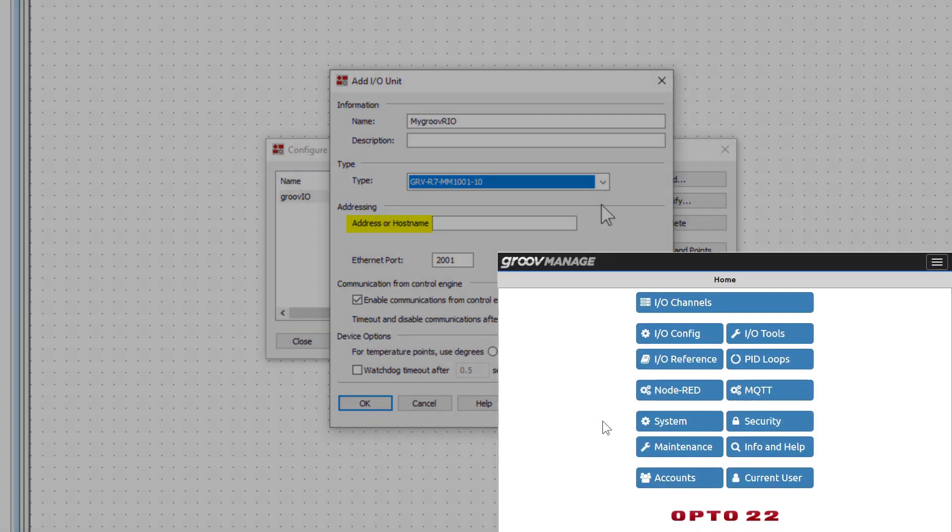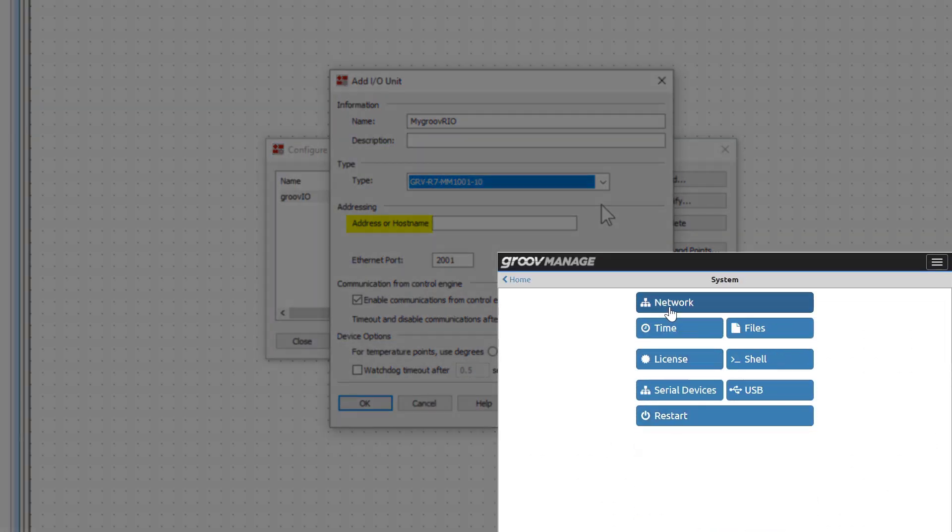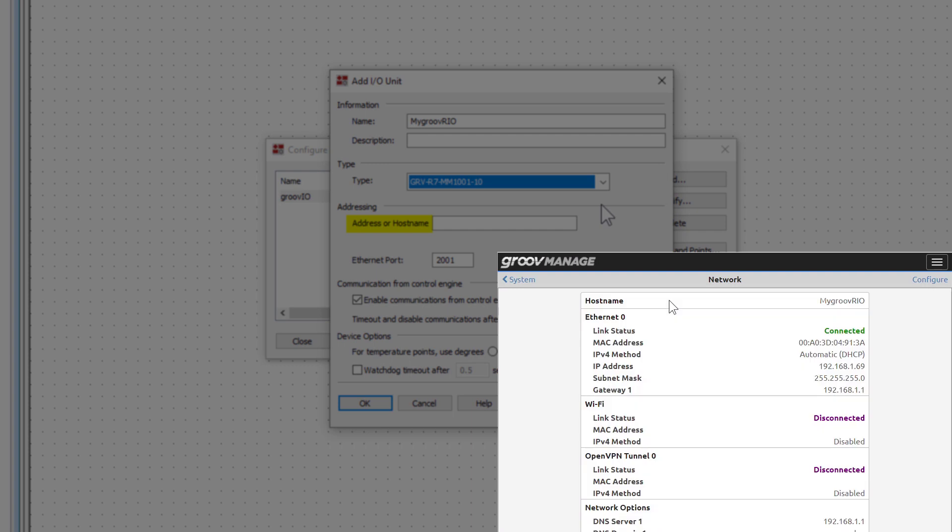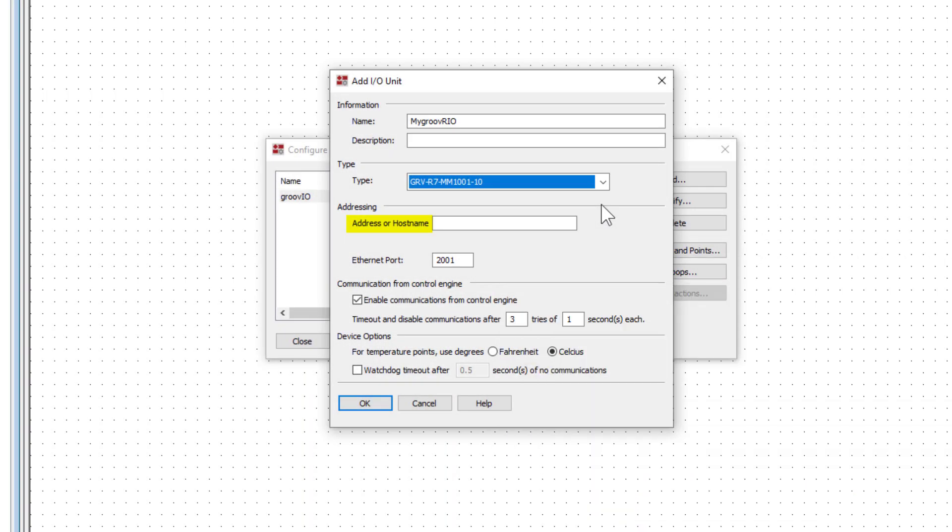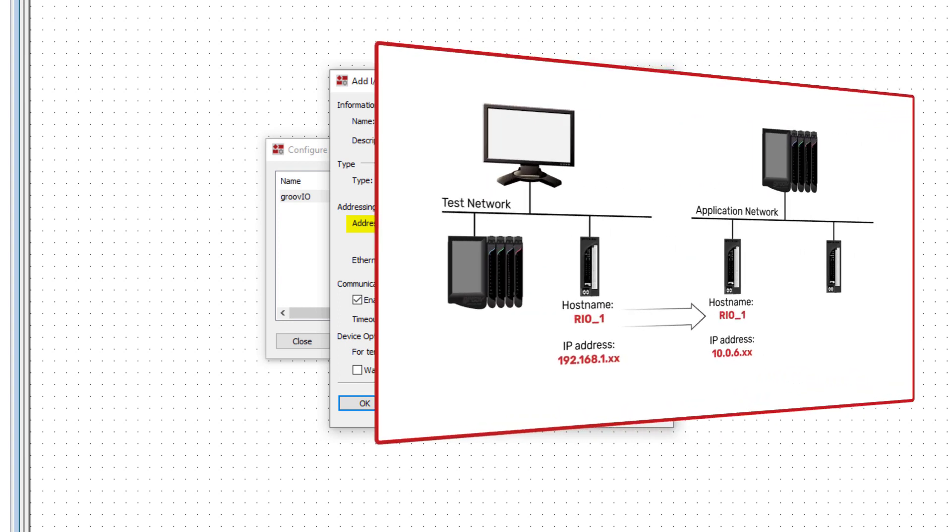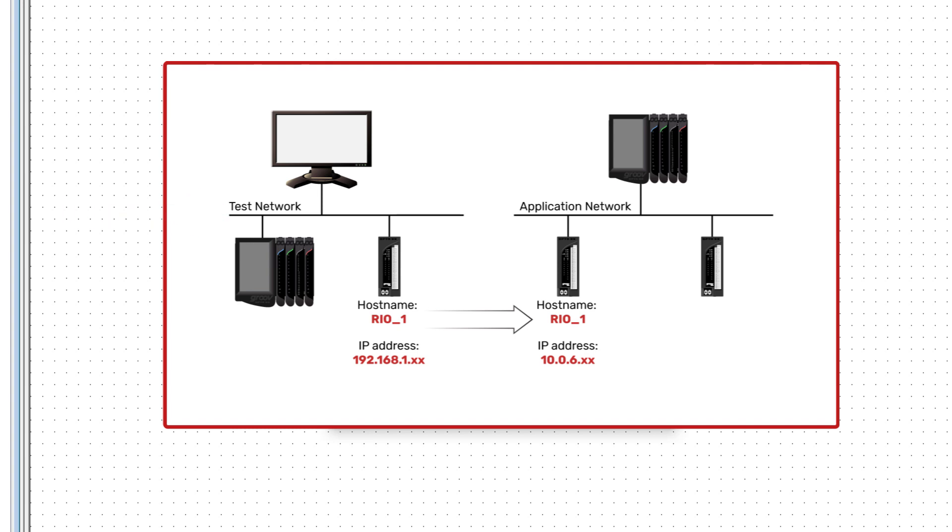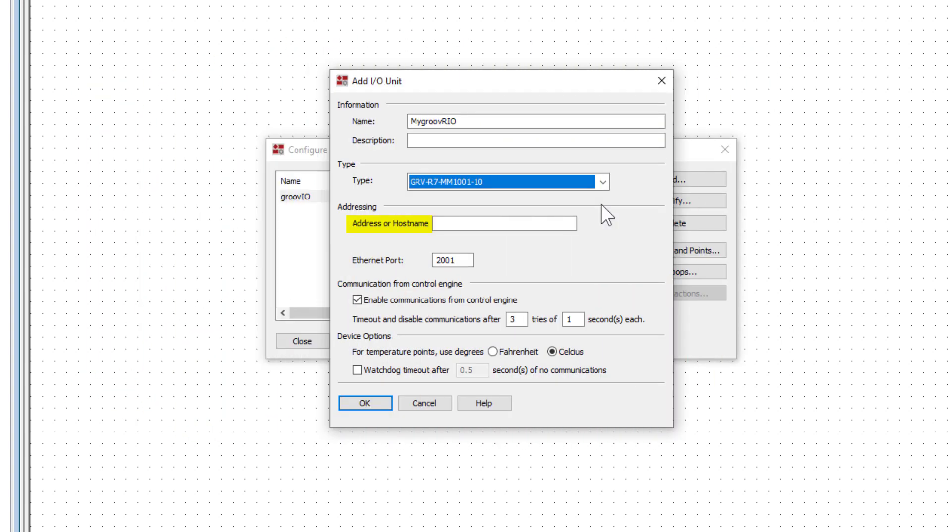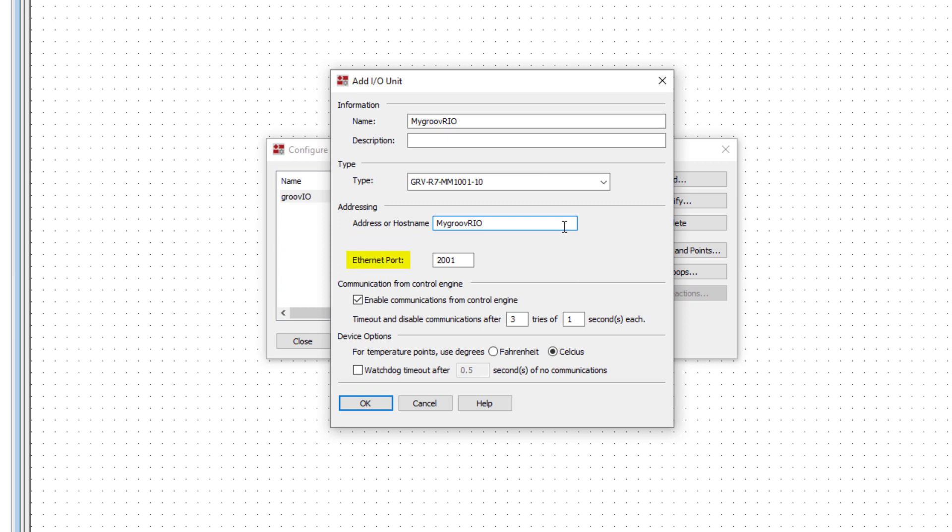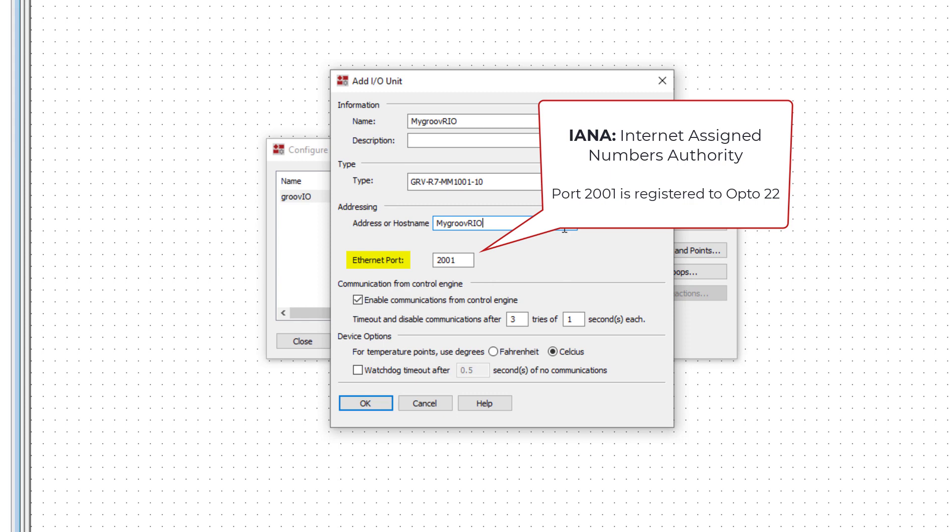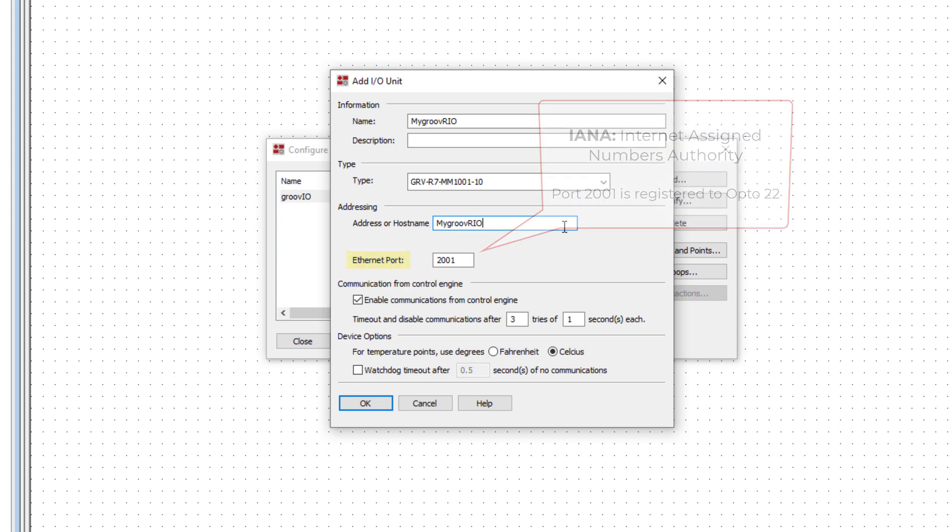I'll switch over to groov Manage for the groov RIO unit. Use the hostname where possible for a couple of reasons. One reason is it's easier to remember than a series of numbers like an IP address. The other reason is if you change networks. It's possible you'll be working on networks with DHCP servers that assign IP addresses. Addresses will vary from network to network. You might develop and test your control system on one network and install your project on a different network. By using hostnames, you don't have to worry about changing the IP address in the configuration. I'll go ahead and use the hostname I've configured. Leave the Ethernet port setting at 2001. That's the default Ethernet port that's assigned to Opto 22 I/O units by IANA.